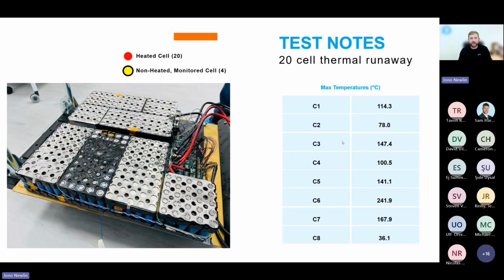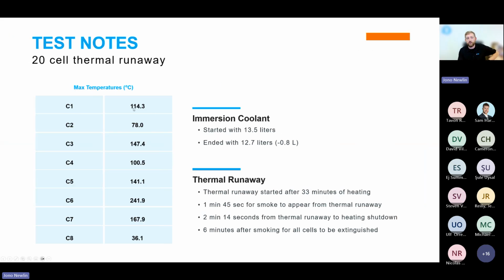I'll highlight this on the next slide: the C1 cell hit 114 degrees at its peak, still below that 150 C threshold we discussed, and it actually had a positive voltage reading afterward. So the cell at the center of all those thermal runaways was protected by the liquid, which dissipated and absorbed the heat in the pack, keeping it from even reaching those dangerous temperatures.